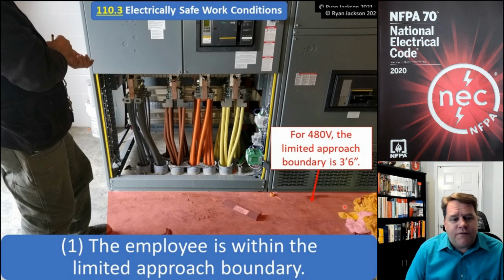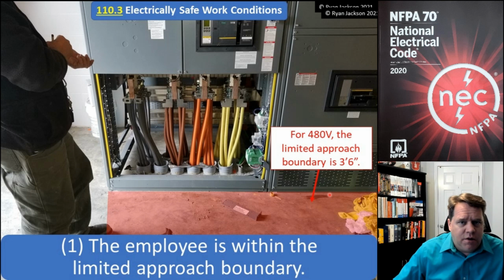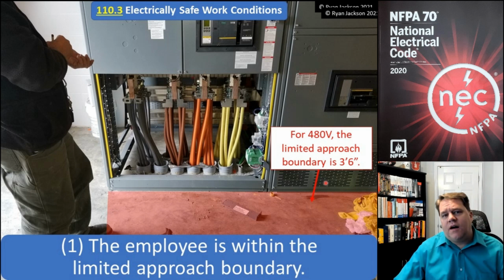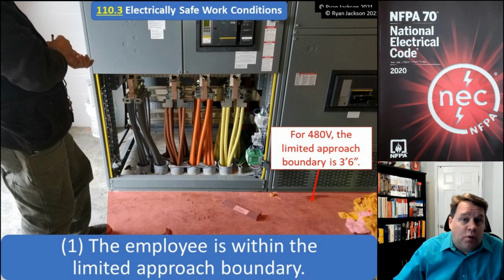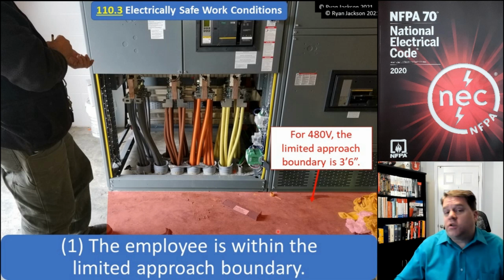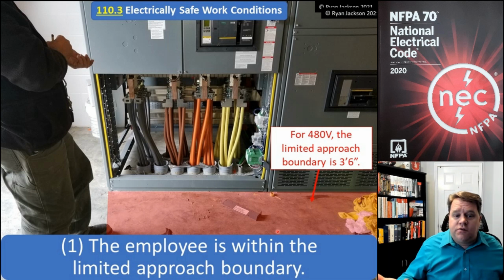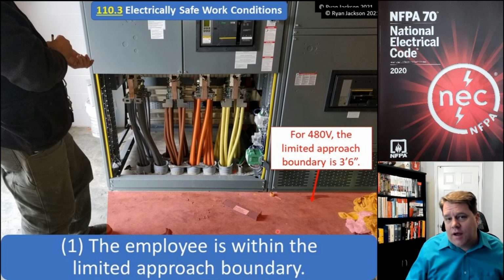So if the employee is within the limited approach boundary, then we need to establish and verify an electrically safe work condition. So what is the limited approach? Well, the limited approach is actually pretty easy to figure out because it's just a voltage issue. For 480 volt, like what we have here in the photograph, the limited approach boundary is 3'6". So if I have the covers off, because with the covers on, there's not a limited approach boundary because there's no shock hazard.